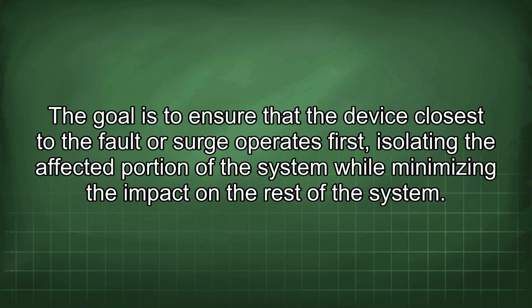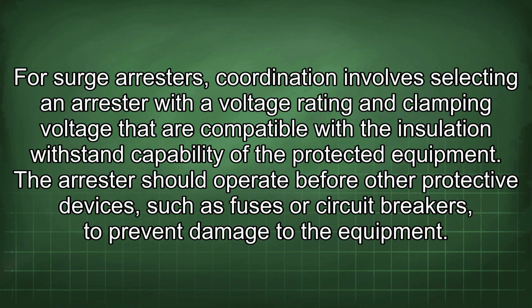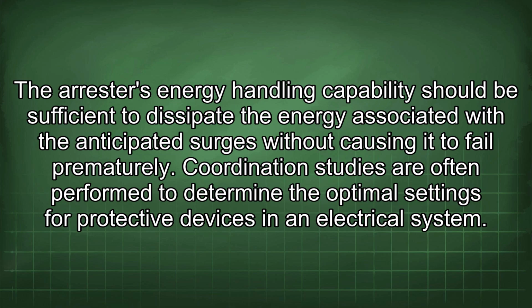The goal is to ensure that the device closest to the fault or surge operates first, isolating the affected portion of the system while minimizing the impact on the rest of the system. For surge arrestors, coordination involves selecting an arrestor with a voltage rating and clamping voltage that are compatible with the insulation withstand capability of the protected equipment. The arrestor should operate before other protective devices, such as fuses or circuit breakers, to prevent damage to the equipment. The arrestor's energy handling capability should be sufficient to dissipate the energy associated with the anticipated surges without causing it to fail prematurely. Coordination studies are often performed to determine the optimal settings for protective devices in an electrical system.